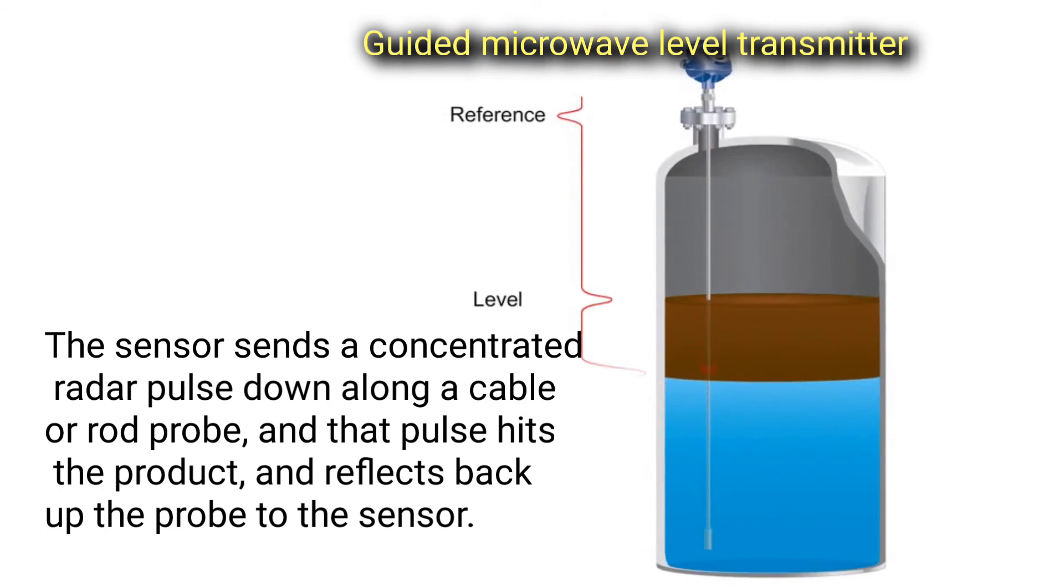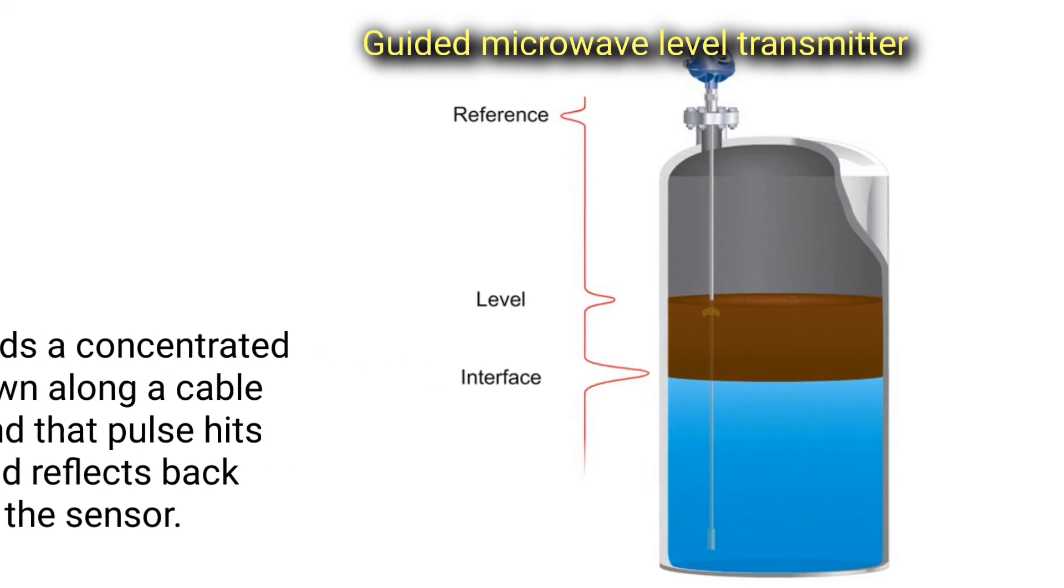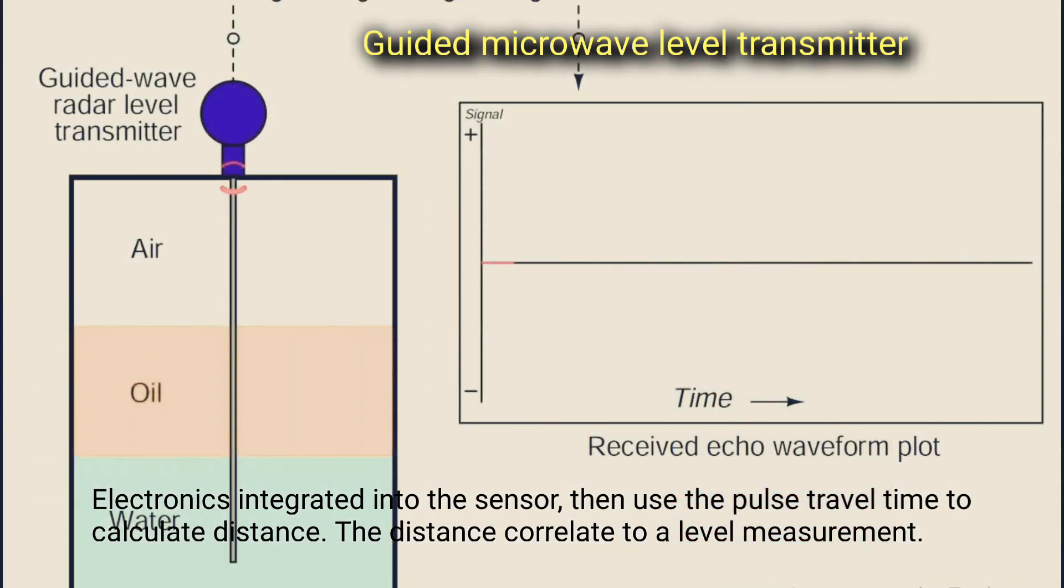The sensor sends a concentrated radar pulse down along a cable or rod probe. That pulse hits the product and reflects back up the probe to the sensor. Electronics integrated into the sensor then use the pulse travel time to calculate distance. The distance correlates to a level measurement.